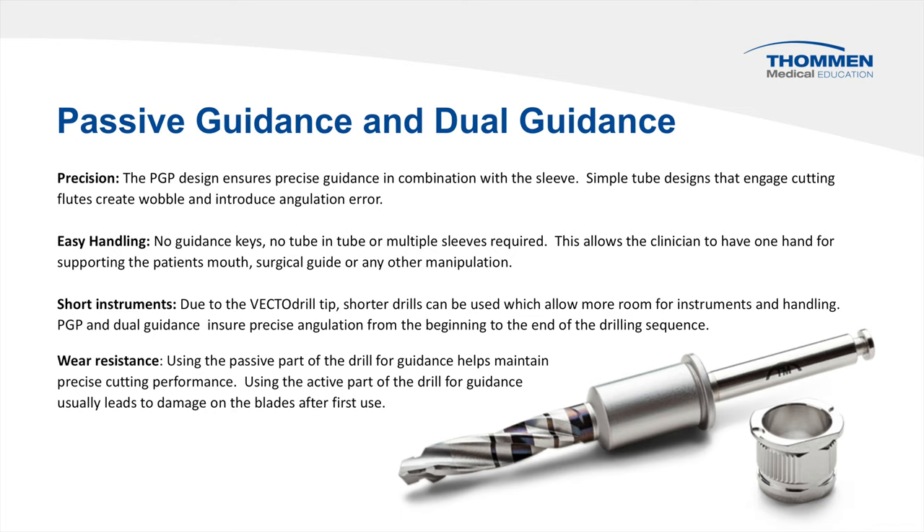The passive guidance principle, in combination with the unique integrated guidance of VectorDrill, provides incredible accuracy in implant placement. The design eliminates the need for guidance keys and tube-in-tube inserts which lead to wobble, angulation errors, and worn drills. Easy handling means fewer as well as shorter instruments, since the PGP design works in conjunction with VectorDrill. Precise performance is maintained since the cutting flutes on the drill never come into contact with the guide sleeve — another benefit of the passive guidance principle.